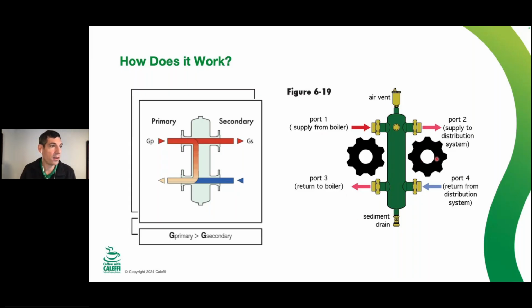So this is spinning and we just have a little bit of water that's going out to the system. So in that case, most of the GPM is just bypassing right back to the boiler. So the boiler is always happy with 10 GPM, even though we have a restriction and we're only sending 2 GPM out of the mechanical room into the distribution for the rest of the building.